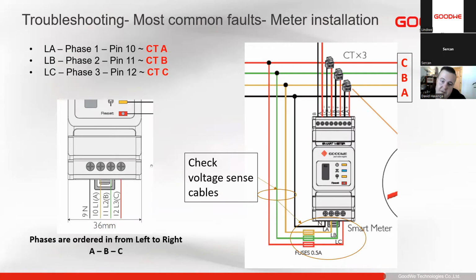It's very important for us to also make sure that this is the correct voltage input for the correct CT. If we have the wrong voltage input for the CT, so if we've put them all from left to right and left to right, then we'll find that A and C will have the wrong voltage input. And when you have the wrong voltage input, essentially you are reading the current out of step. So then it will see that current, probably 50% of the active power will be read, and we'll also see it in the wrong direction.